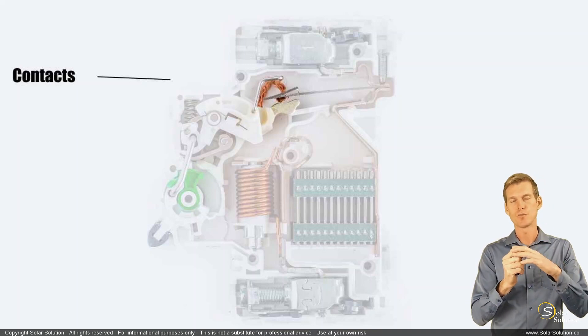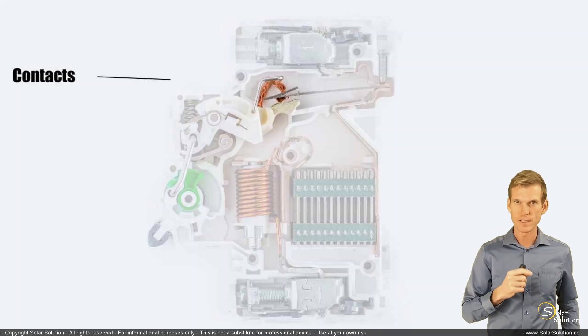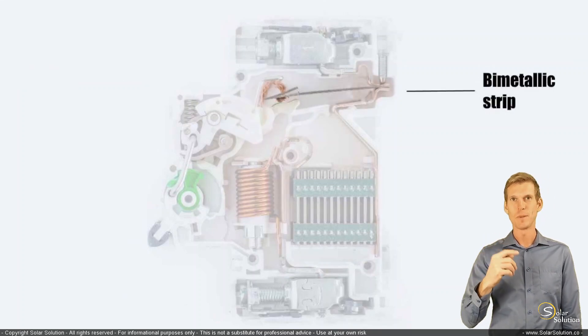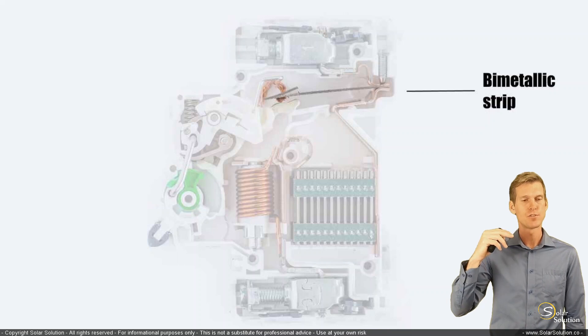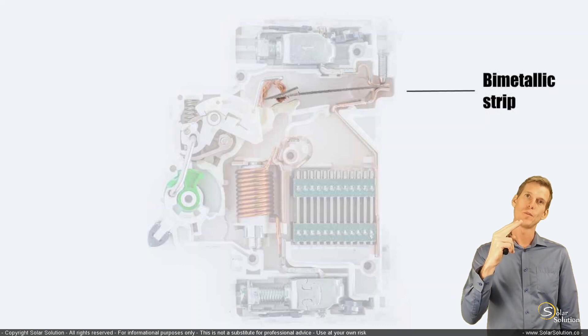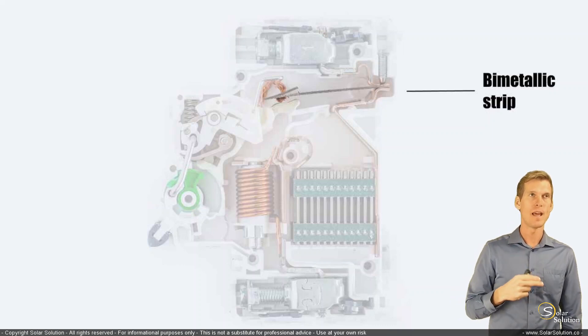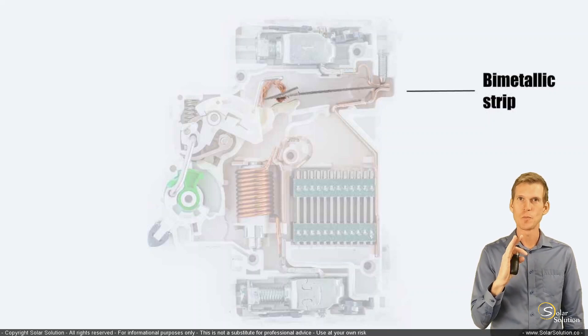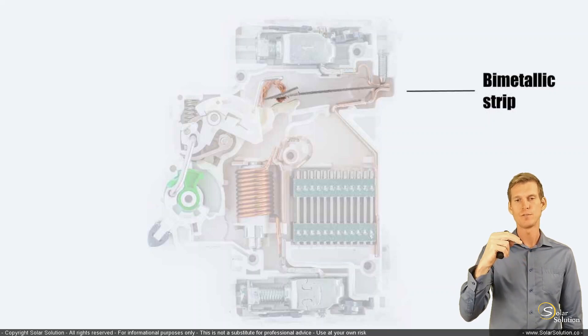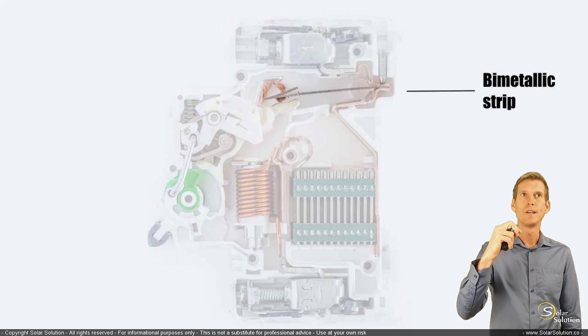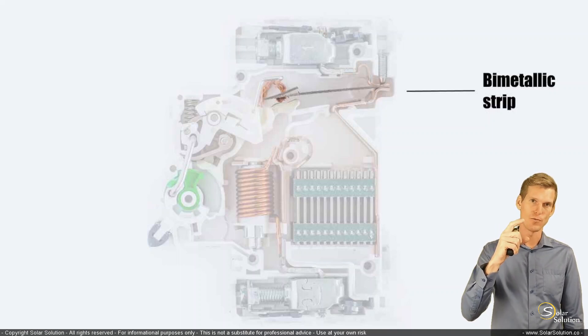The lever and mechanism together control the contacts. You can also see the bimetallic strip — a strip made of two metals. If a certain amount of current passes through it, it tends to bend in one direction. The bimetallic strip allows for the slow tripping current: if current is in the range that would normally trip the breaker, the strip heats up and slowly starts to bend more and more until it trips open the contacts and disconnects the circuit.